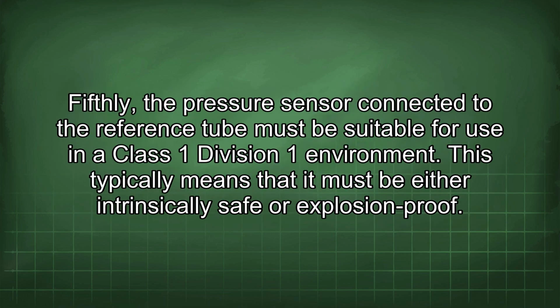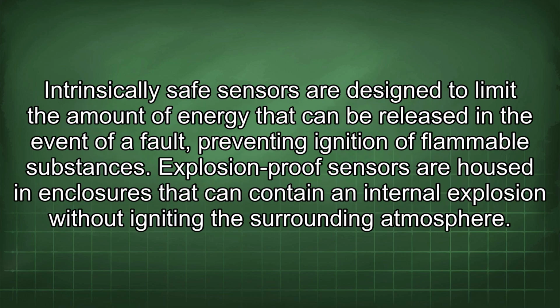Fifthly, the pressure sensor connected to the reference tube must be suitable for use in a Class 1 Division 1 environment. This typically means that it must be either intrinsically safe or explosion-proof. Intrinsically safe sensors are designed to limit the amount of energy that can be released in the event of a fault, preventing ignition of flammable substances. Explosion-proof sensors are housed in enclosures that can contain an internal explosion without igniting the surrounding atmosphere.